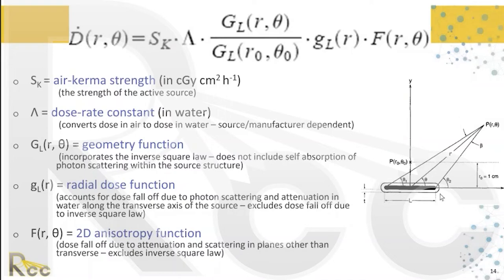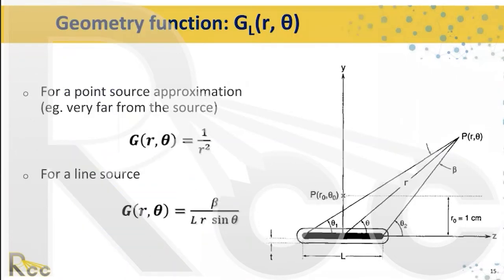The 2D anisotropy function accounts for differences in scattering in different planes based on how the source is built. For a spherical source the anisotropy is one, the same in any direction, whereas cylindrical sources have an anisotropy factor that matters especially when the dose calculation region is close to the source. The geometry function for a point source approximation is essentially the inverse square, but for a line source you also account for the angle subtended at the source.